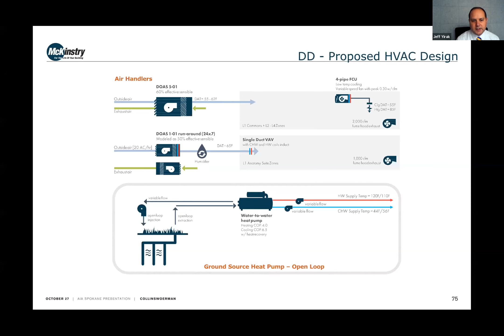Flexibility was the name of the game with this systems design. We can accommodate a range of occupancies and conditions within the space, so whether you've got 10 people in the classroom or 100, we can keep you comfortable. Whether there's a wildfire smoke event or it's flu season, we can deliver filtered air for all the occupants. These systems were designed to the latest guidance and recommendations from ASHRAE, including publications that just came out last month. So this was not a business as usual design.